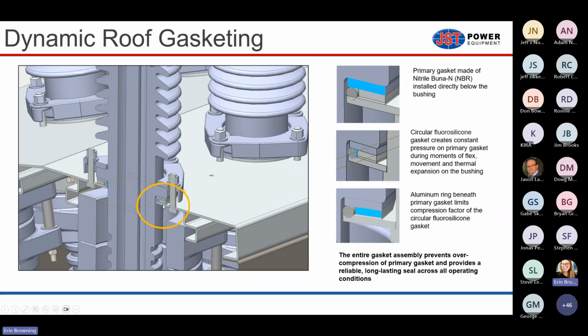So you have this kind of reinforced gasketing system so that the bottom surface of the bushing is always flush with the roof, and you don't have cracks and seams tearing as the overhead cables are moving or twisting in the wind, or when you have the physical bounce of the vacuum bottles when they open and close. You don't have any opportunity for water and sand or whatnot to get into the roof of the circuit breaker.